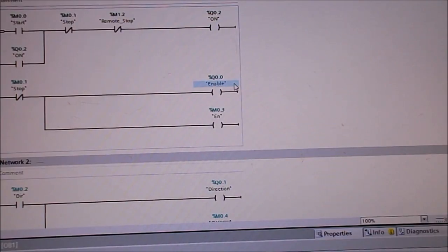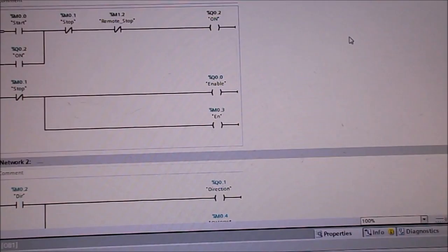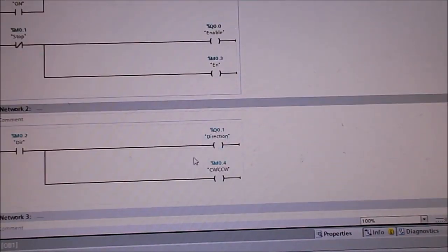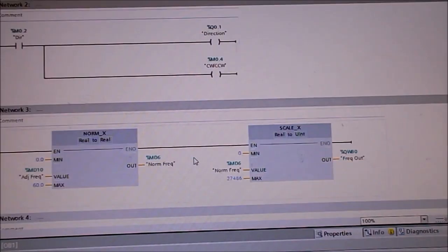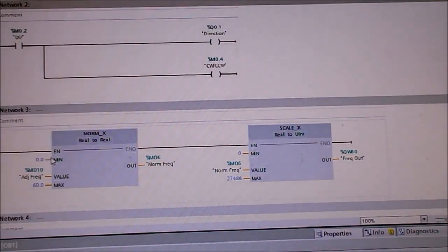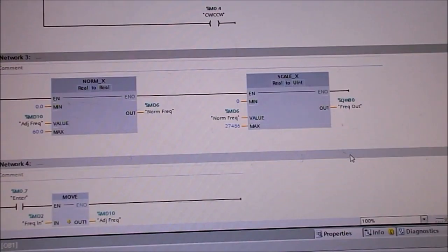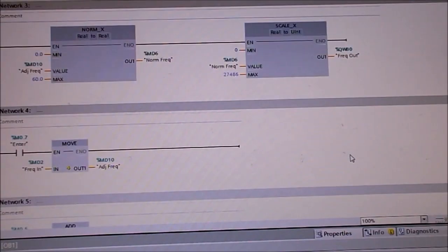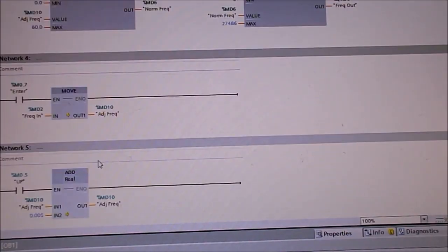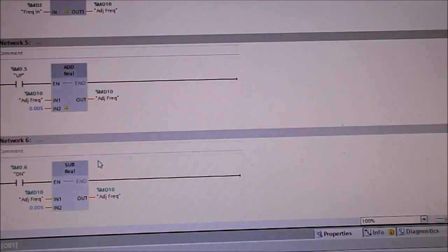This shows part of the ladder logic. We have a simple latch circuit to get it running. We've got direction, and then we've got an analog card in here so we can take our input for speed control and convert it to an output frequency. We have some buttons that we can use to adjust the frequency up and down in slight increments.